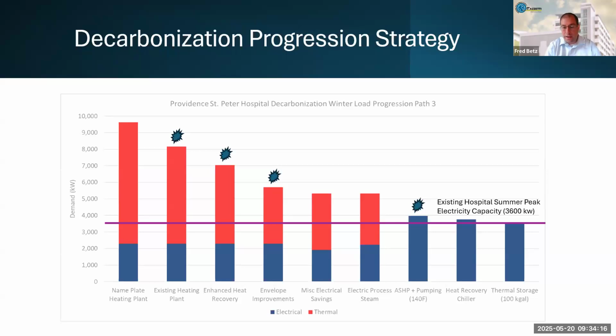There is, again, metered 60 tons of heat recovery chiller. Heat recovery chillers are another technology that a lot of folks don't like because they don't work properly. And the number one reason they don't work properly is because they've been sized wrong. They need to be sized small, not large, which is antithetical to how most mechanical equipment is designed. It is sized to be large, and you can always turn down from there. Heat recovery chillers need to have a place to go with both the cooling and the heating. And so since we know what the loads are, we know that a 60-ton heat recovery chiller is exactly what we need, and that will run flat out and won't have cycling issues and so on. So again, we're reducing our heating load a little bit off that 60-ton unit.